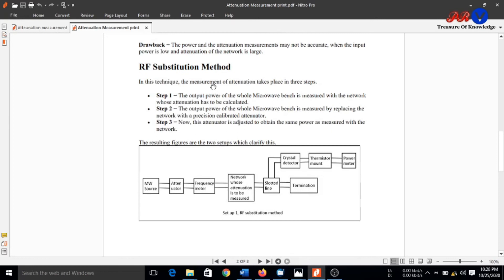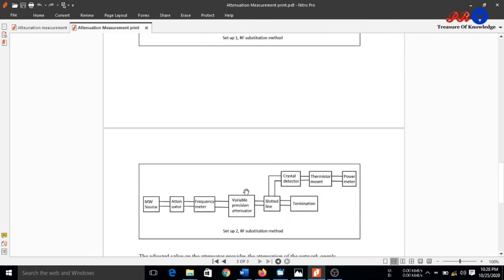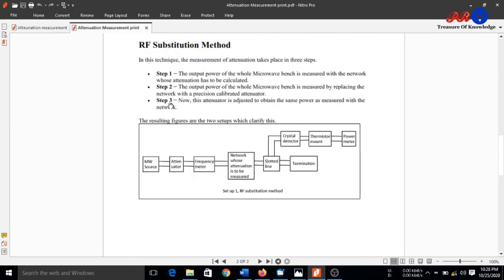In the RF substitution method, we use three steps. In step 1, the output power of the whole microwave bench is measured with the network whose attenuation has to be calculated — meaning we connect the device under test and measure the output power. In step 2, the output power of the whole microwave bench is measured by replacing the network with a precision calibrated attenuator — this standard variable precision attenuator replaces the device under test.